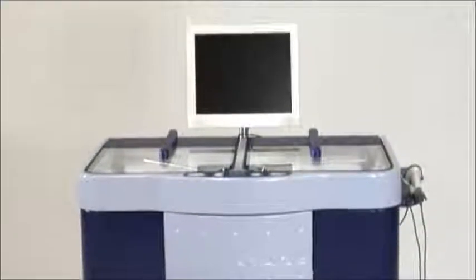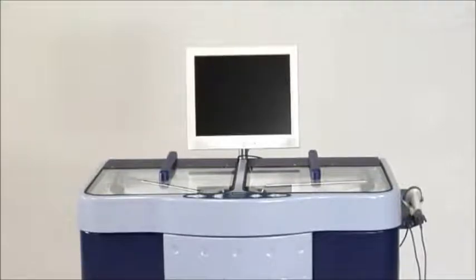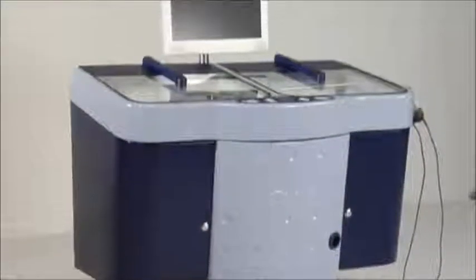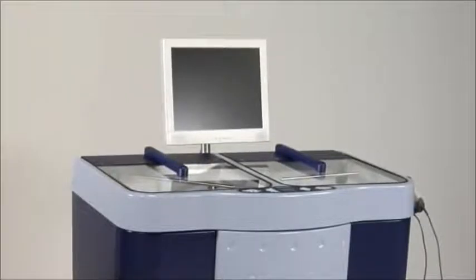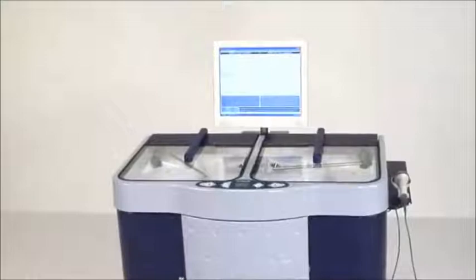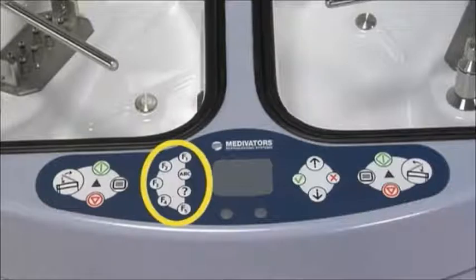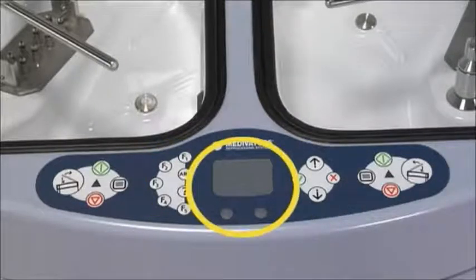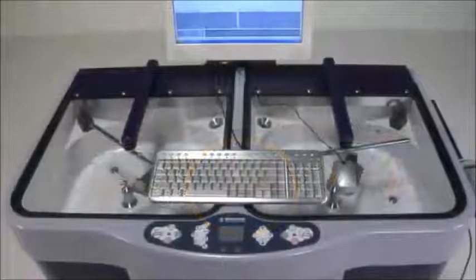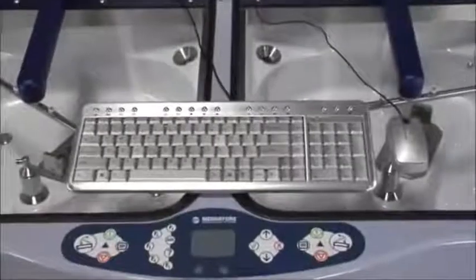There are several components that are shared by each module. The computer, or CPU, manages the reprocessing cycles and data storage completed in each module. Depending on your unit, the CPU may be either combined with a monitor or separate and located in the back of the Advantage Plus. The monitor displays in a split-screen format for easy viewing of each basin's cycle information. For example, the left side of the screen displays the cycle information being performed in the left basin. The monitor also displays in a full-screen format for cycle data management and information entering. The control panel consists of function keys, selection buttons, and a touchpad and mouse buttons. A keyboard and mouse are also supplied with the Advantage Plus and can be connected for use when entering user information.